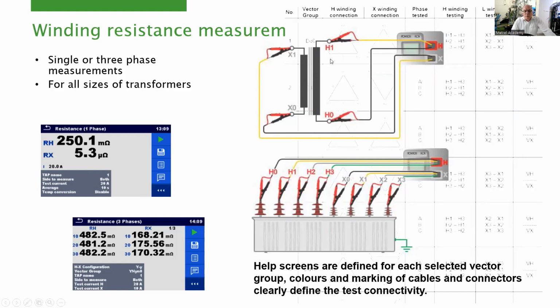So between one measurement and the next, we don't need to switch the clamps from one terminal to another. We connect once, perform all the needed measurements, and then disconnect the cables. Cables are colored, terminals are colored, connectors are colored, so you cannot make a wrong connection. And if you're not sure you're doing it correctly, you always have help screens like this on the screen, so you can connect the cables without doubt.